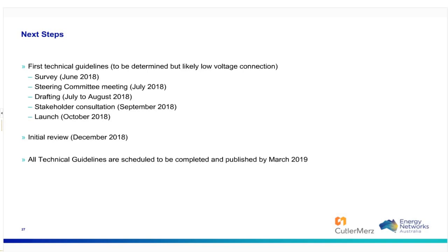I think the next two are details, which I'll skip for now. The next question, Stuart, do you want to answer that one? The question is that basic connection service limits may be appropriate for urban networks but will cause issues on SWER or single-phase rural networks. Yes, we realised that, and part of the process identified that if there was an issue in some areas, justification by the network could be made that alternate settings needed to be put in place, and that could happen through this process. It just needs to be justified why that would be different on a SWER line or single-phase rural network compared to an urban network.